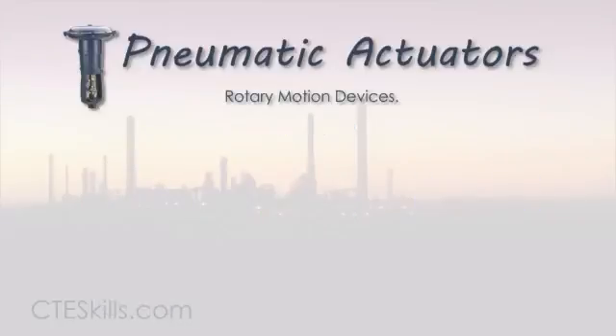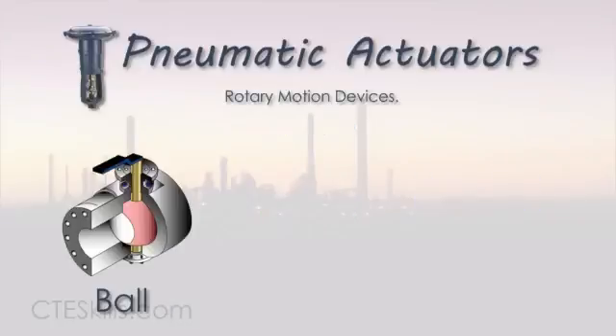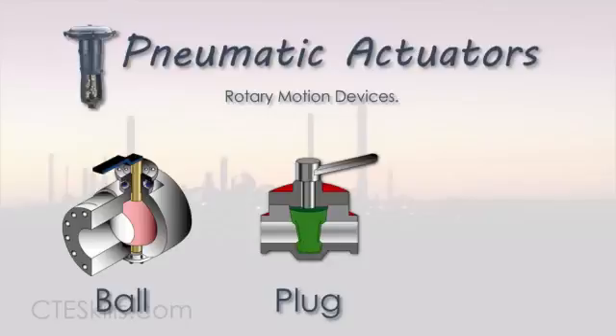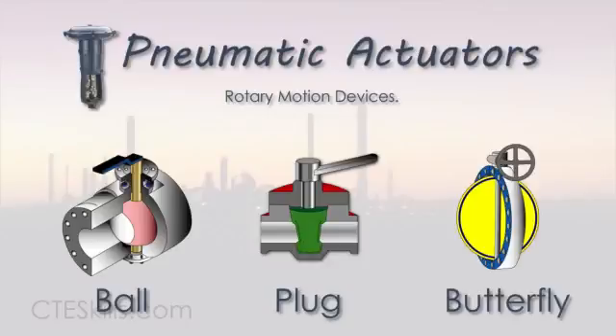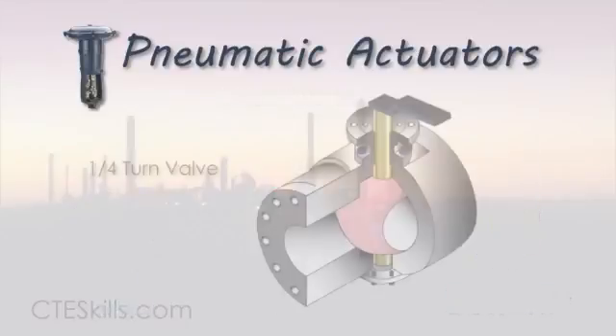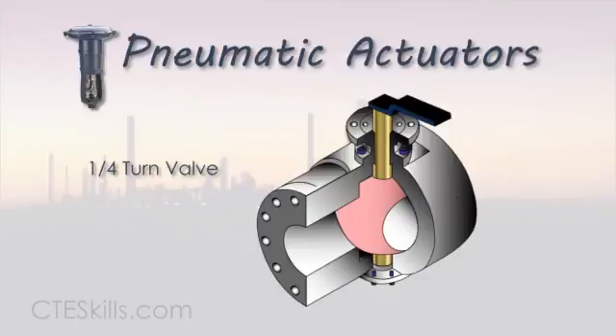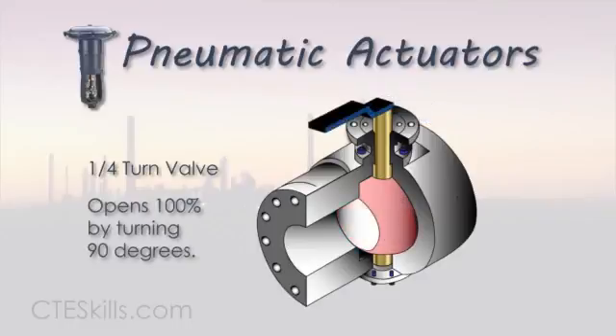Rotary motion typically operates quarter-turn type valves such as ball, plug, and butterfly. A quarter-turn valve is one which can be opened 100% by turning the flow control element just 90 degrees.